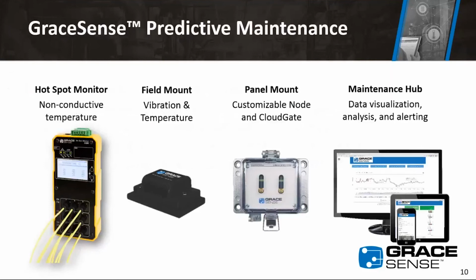Here's a look at the hardware in our predictive maintenance system. I'll go into each of these in detail, but on the left you have the hotspot monitor. That typically sits in your low voltage compartment in switchgears or MCC equipment, with a probe routed out to a connection so you can continually monitor temperature.